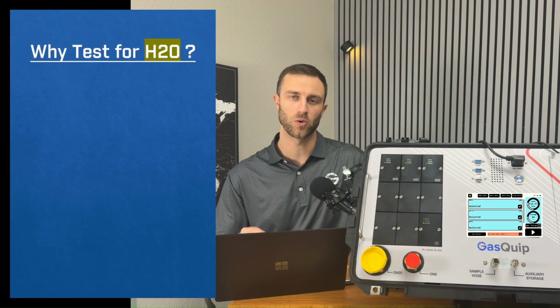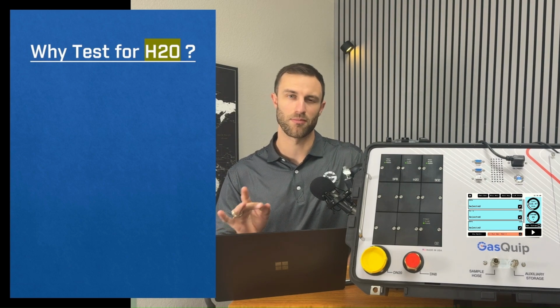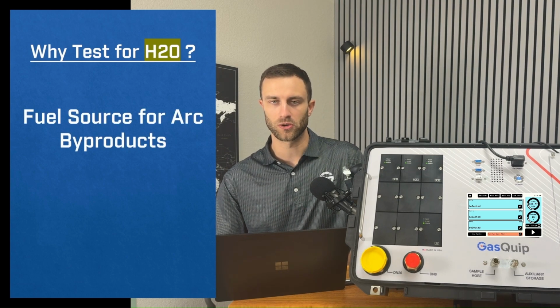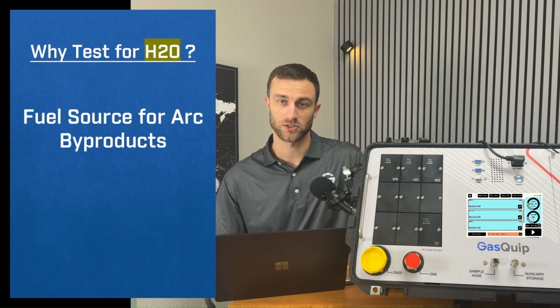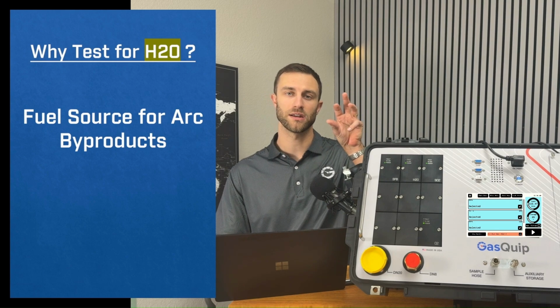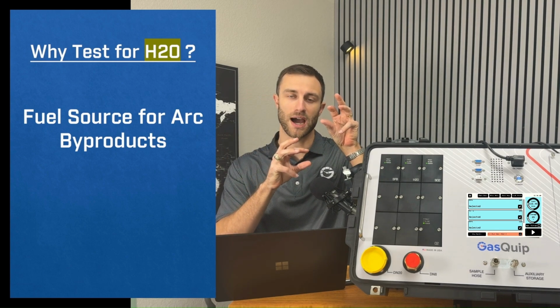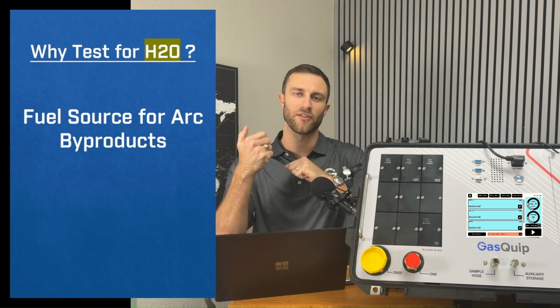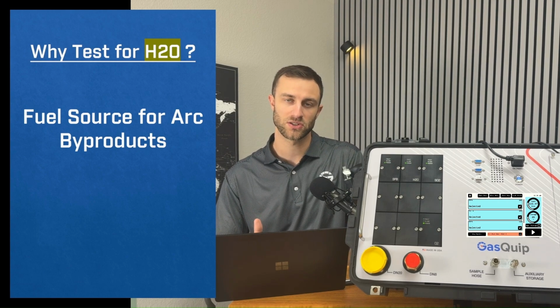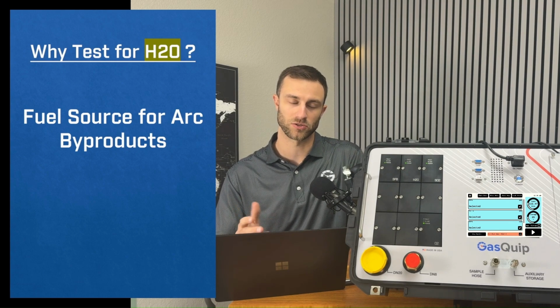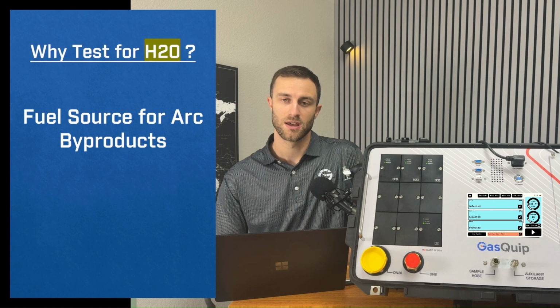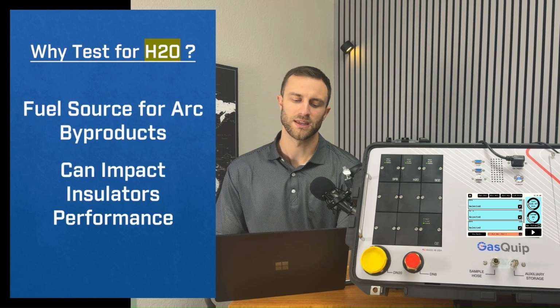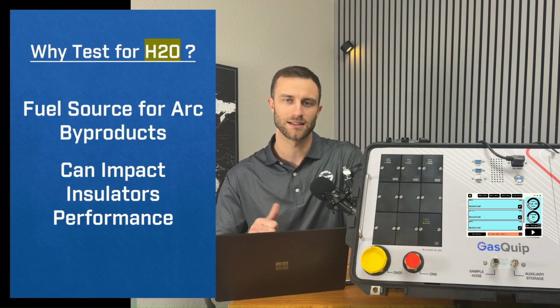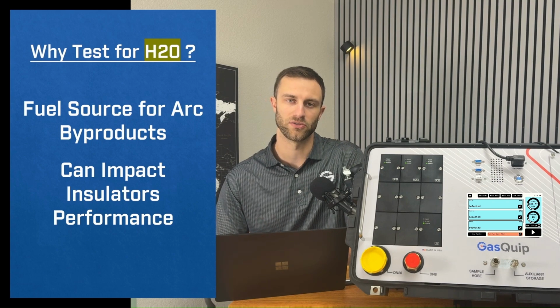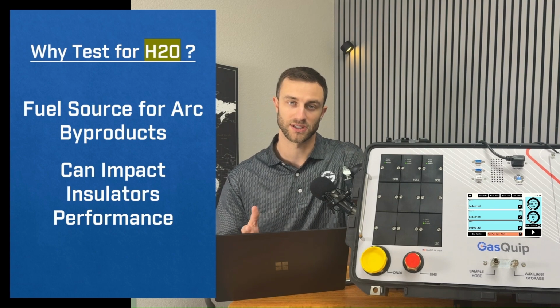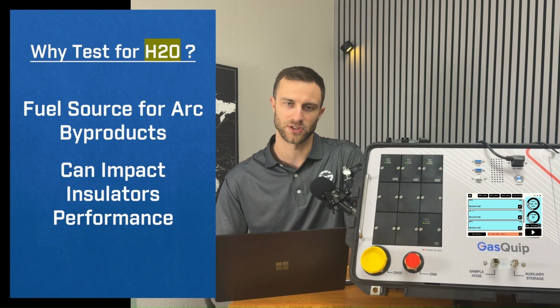Why do we test for H2O or dew point or moisture? Well, there's one main reason and then there's a minor reason also. The main reason is that H2O or moisture is a fuel source for arc byproducts. So what that means is when you take sulfur hexafluoride, you take water, H2O, and then you mix that with a high heat or high energy event, you can spit off some nasty acidic compounds that are very dangerous for the operator and then also for the equipment and its long-term health. And we'll talk about some of those arc byproducts in a second, but the minor reason is that H2O can impact the insulator's performance at high levels of moisture, generally above 1,000 ppmv of moisture. So those are the two main reasons that we actually test for dew point or ppmv if you're using that of moisture.